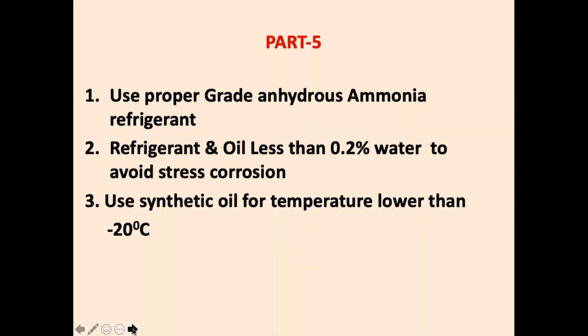The last part: use proper grade anhydrous ammonia refrigerant. There should not be water in the refrigerant and oil, less than 0.2%, to avoid stress corrosion. Remove water; there are water rectifiers available. Use synthetic oils for low temperatures below minus 20 degrees centigrade so that your discharge temperature is within limit, and these synthetic oils can withstand much higher temperature than mineral oils, up to say 170, 180 degrees centigrade.